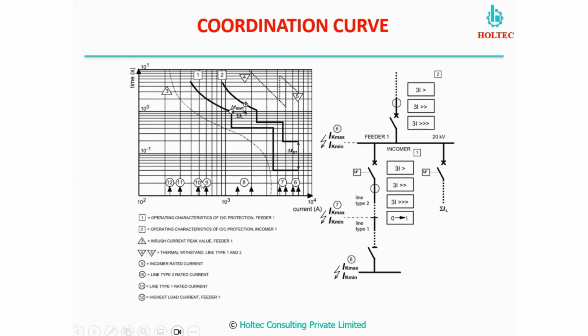In that way, over the entire range of the fault current, we are in a position to validate that relay 2 will never operate before relay 1. So this we can achieve. There we can have 100% surety, 100% reliability with respect to the coordination which we can ensure. Not only this, in this curve we can also get these lines.